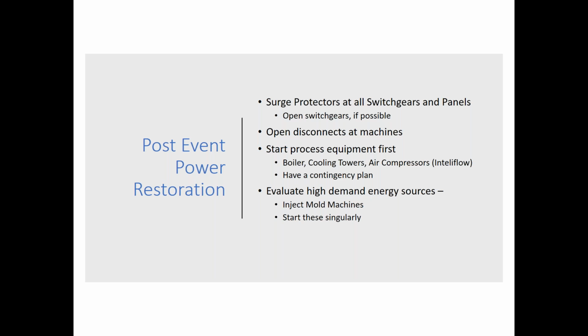During these shutdowns, if the power's out for a long enough period of time, we have a small team that goes out automatically with a check sheet for just about everything. They'll go out and open switch gears, and if time permits, open all the disconnects on all the machines, so that when we come back to start up our processes, we're not hitting all that power at one time.